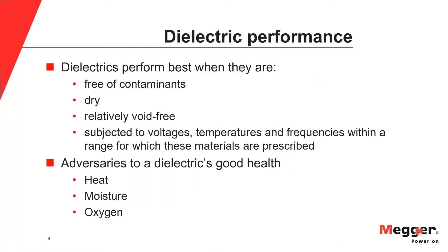Insulating materials prevent real or resistive current flow and support an electric field best when they are free of contaminants, when they're dry, and when they're relatively void-free — which emphasizes the importance of satisfactory oil impregnation. Keep in mind that solid paper insulation in a transformer has inherent voids, so it's important that oil fills these voids completely to avoid breakdown of the field across them.